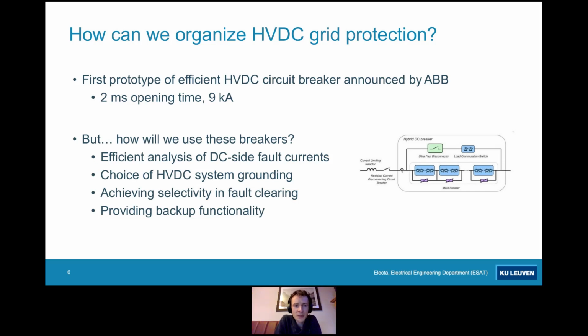But there was still a main question. So how will we use these breakers? This was the main topic of my research. So we needed efficient means to analyze DC side fault currents in extensive HVDC grids. There was also the question of the choice of HVDC system grounding. So we can go for a low impedance grounded system or a high impedance grounded system, each with their advantages and disadvantages.